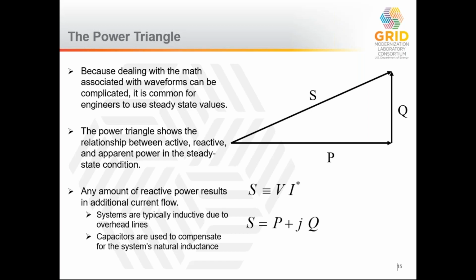When you talk about different equipment in electric power systems, they have multiple ratings. Typically, things like transformers are rated in apparent power as either kVA or MVA—kilo or million volt-amperes—because what you're really looking at is the thermal ability for that equipment to carry current.